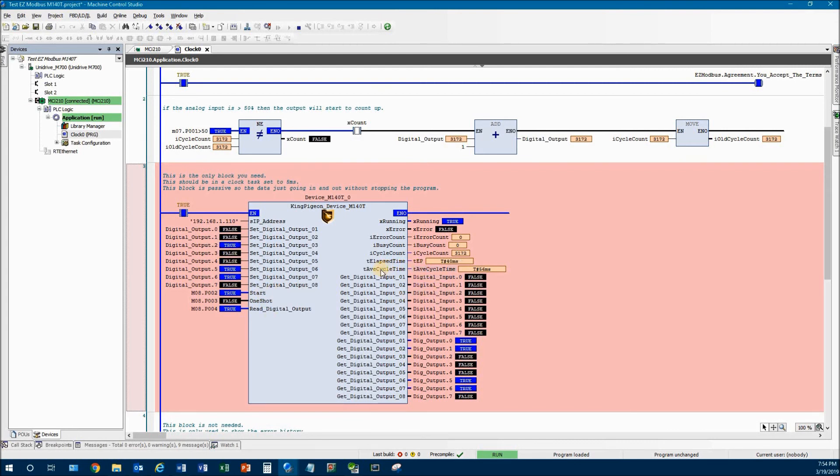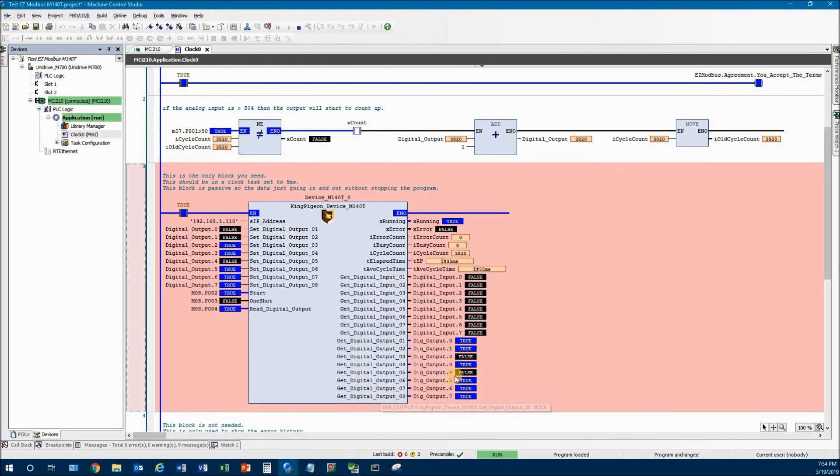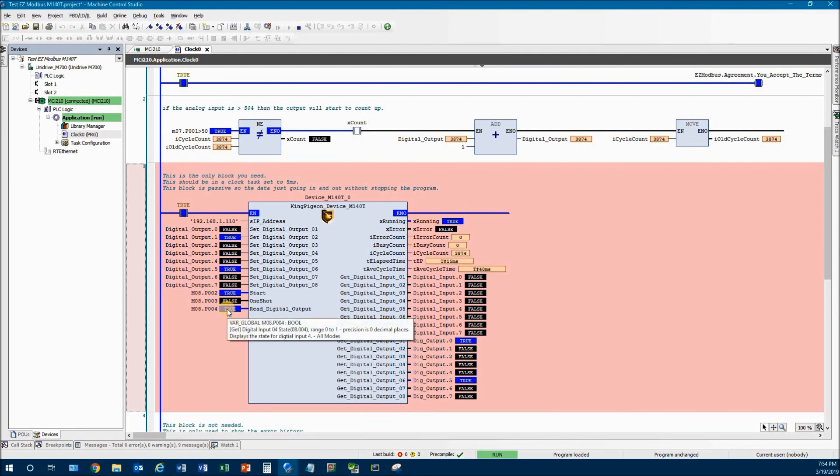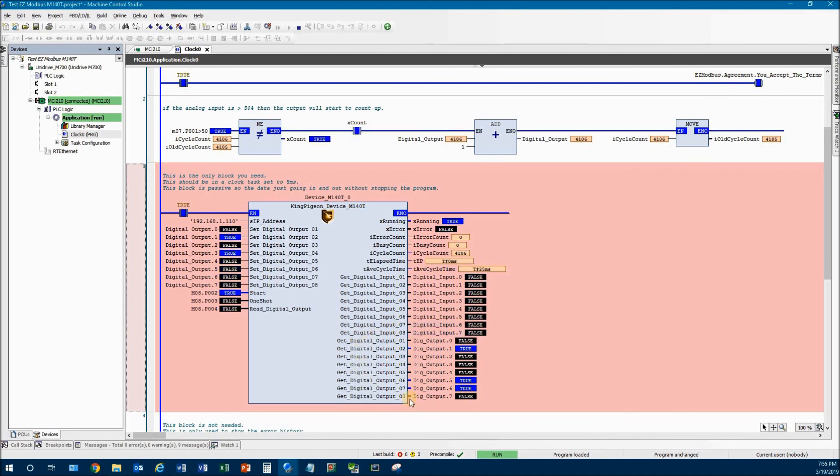Also, here's the average time. What the average cycle time is telling you is that it's the amount of time it takes for it to send this, read this data back, and read this data back. You'll notice that if I turn off 804, which is the digital output, that this goes to a lower value. And that's because it's no longer wasting time reading this information back out of the bus coupler.